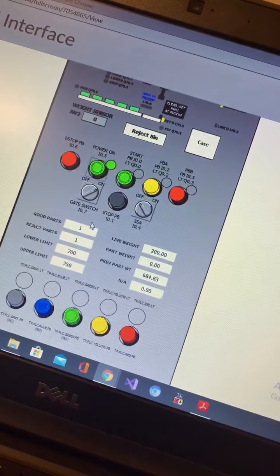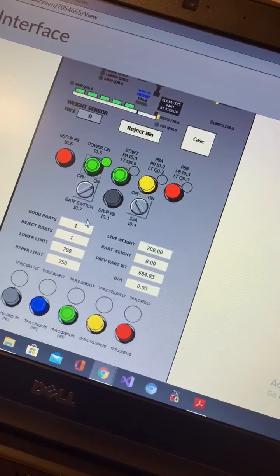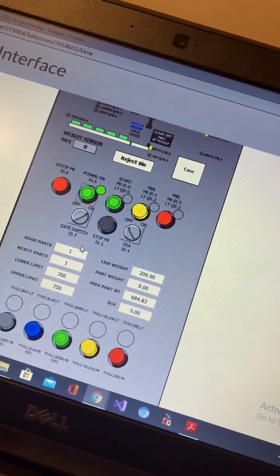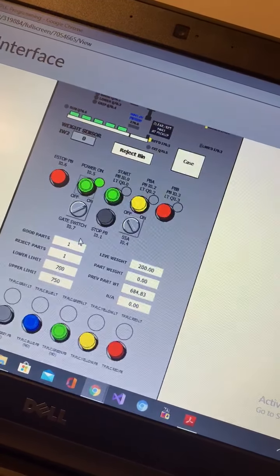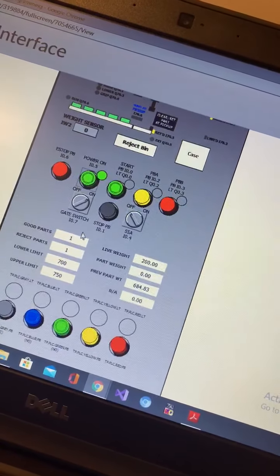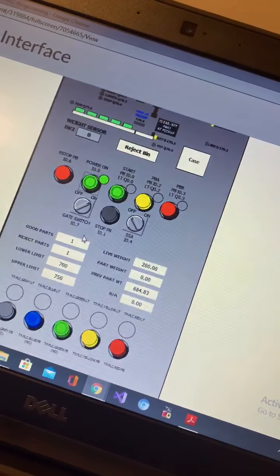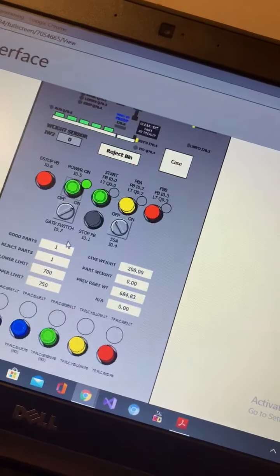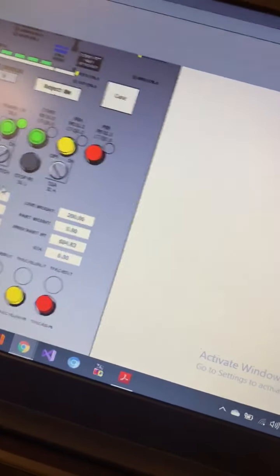So in my production statistics, when the blue light turns on, it counts the number of good parts, and I used a CTU instruction in that part. So when my reject bin turns on, it counts the number of bad parts, and I used a one shot and add instruction in that network. So my good parts are shown in integer 3 and bad parts are shown in integer 4. I used a move instruction for that. So when the part is picked up, it counts the total parts, so I used a CTU instruction for that.